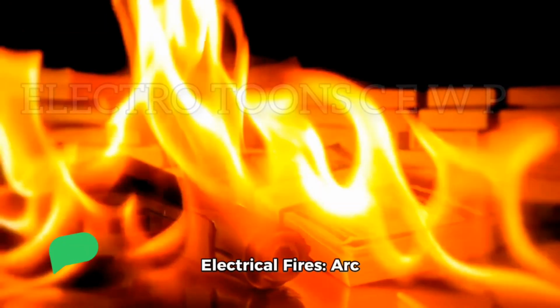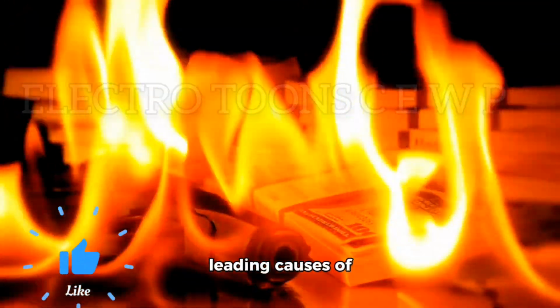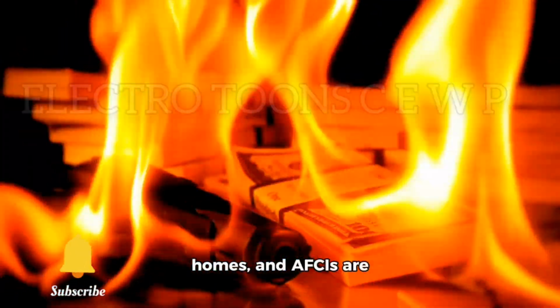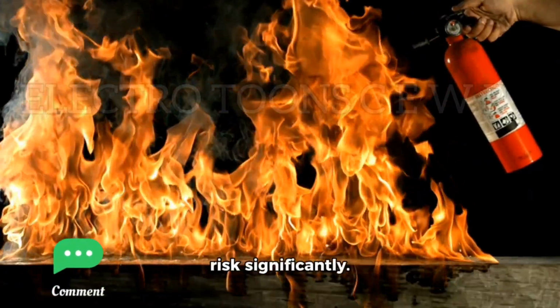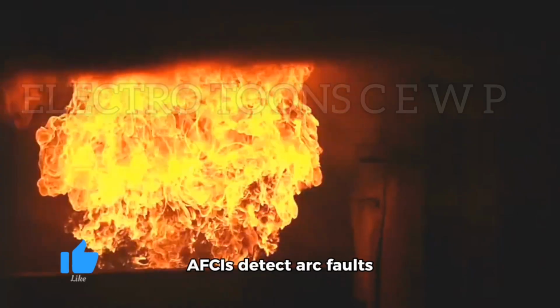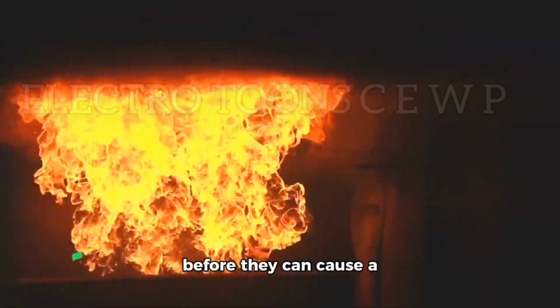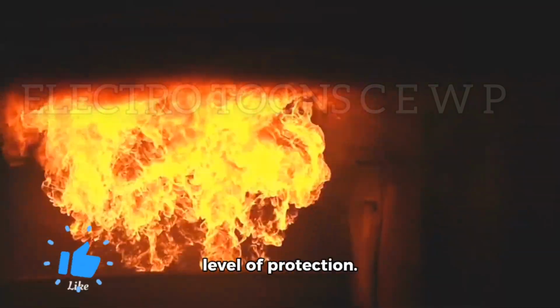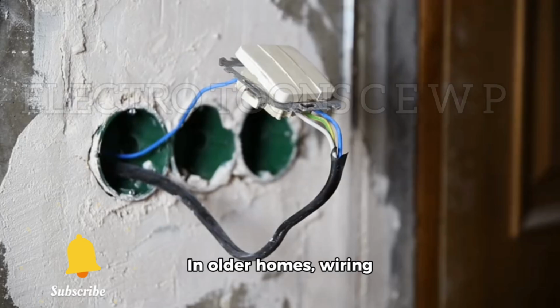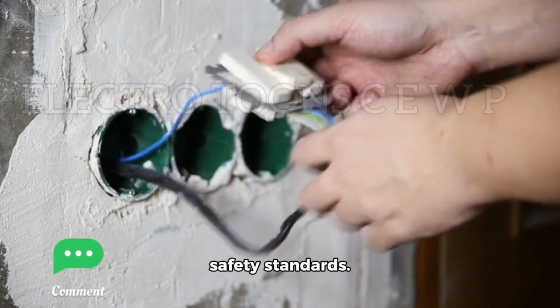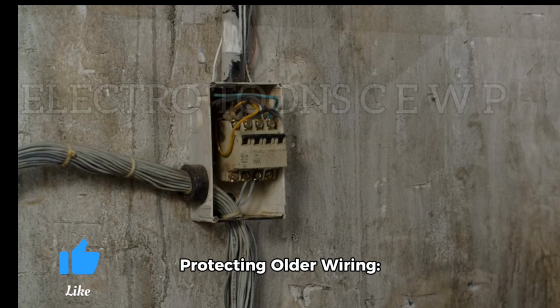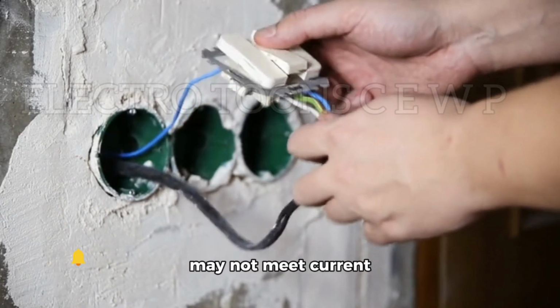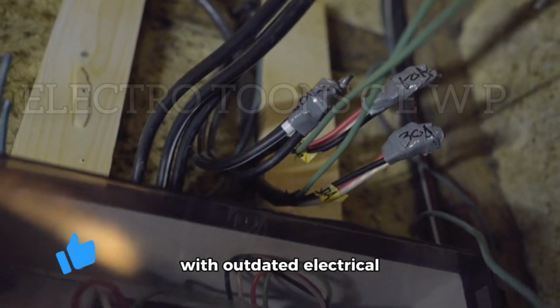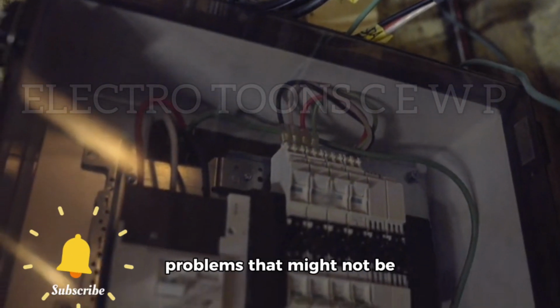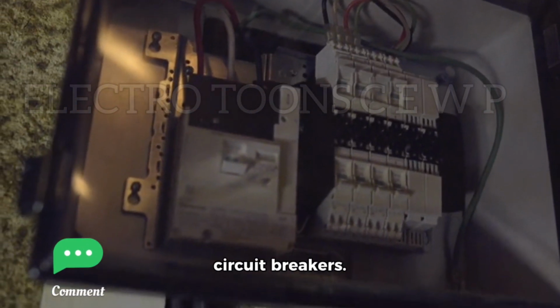Here are some key reasons why AFCIs are important. Prevention of electrical fires. Arc faults are one of the leading causes of electrical fires in homes, and AFCIs are designed to reduce this risk significantly. Early detection. AFCIs detect arc faults in their early stages before they can cause a fire, offering a high level of protection. Protecting older wiring. In older homes, wiring may not meet current safety standards. AFCIs help protect homes with outdated electrical systems by detecting problems that might not be apparent with older circuit breakers.